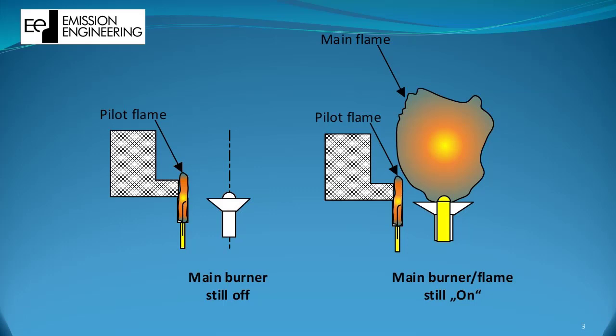No doubt, flame detection by ionization of pilot burner is a valid detection method for the pilot. But pay attention, it is not a fully valid method for the main burner. What does that mean?